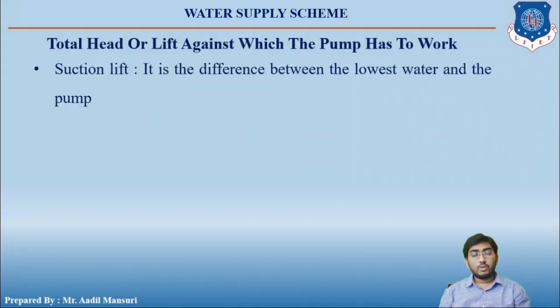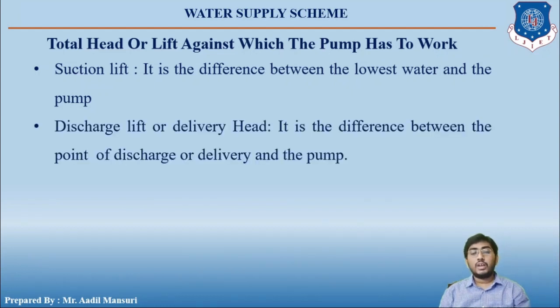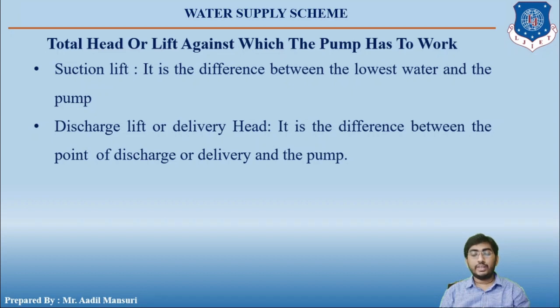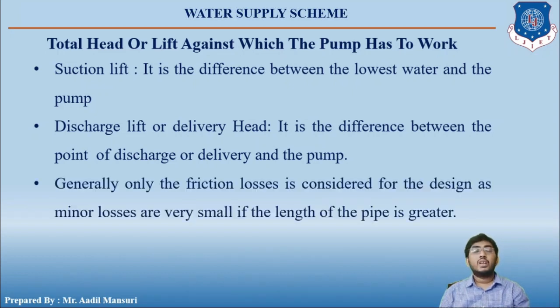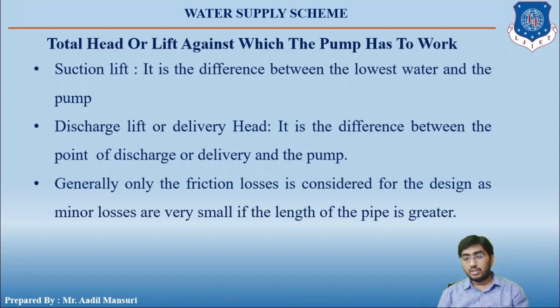The suction head is the difference between the lowest water level and the pump. The discharge or delivery head is the difference between the point of discharge and the pump. Generally, only the frictional losses are considered for the design, as minor losses are very small, especially when the length of the pipe is greater.